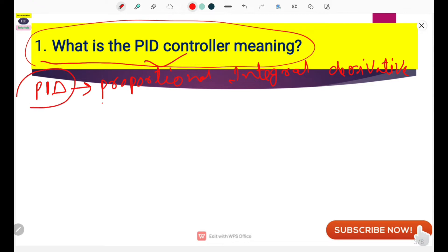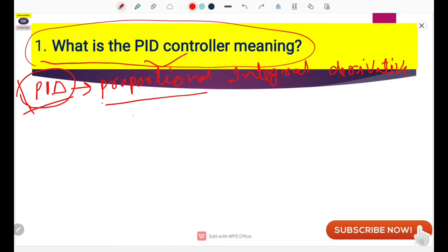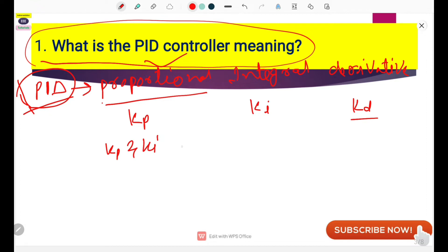The PID controller is actually installed or configured in a PLC. PID controllers are also available as standalone units in the market, which you can install in your plant to regulate or control your process parameters. In a PLC, the control gains used are: Kp for Proportional, Ki for Integral, and Kd for Derivative. Generally, when controlling a process parameter, two parameters are used and one parameter is set to zero.